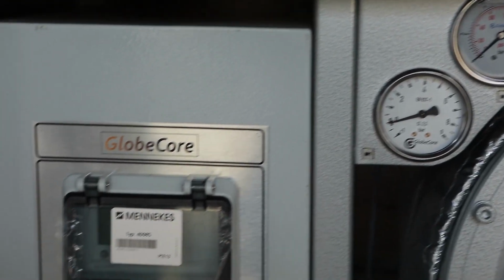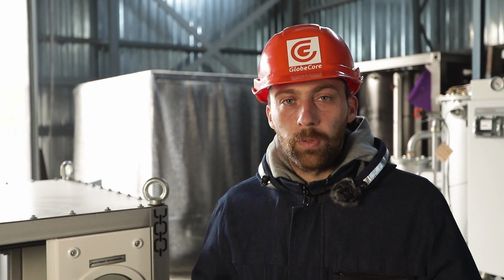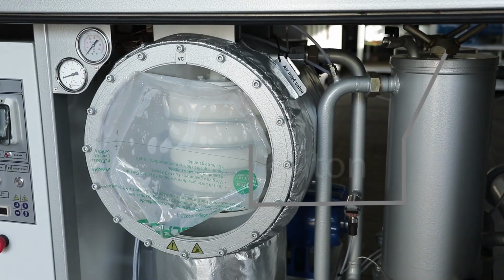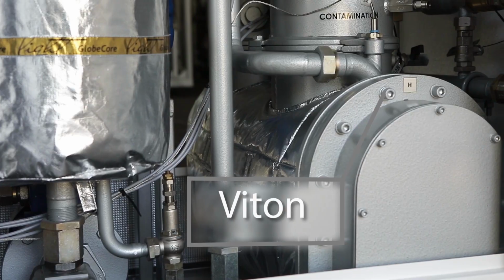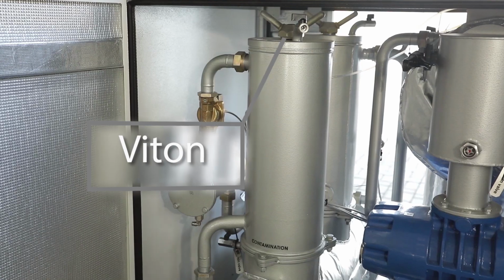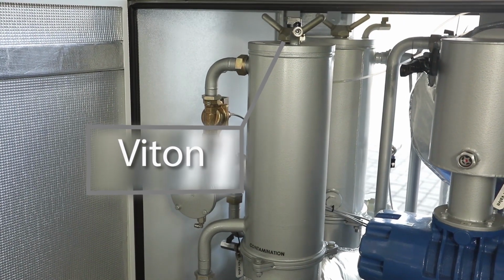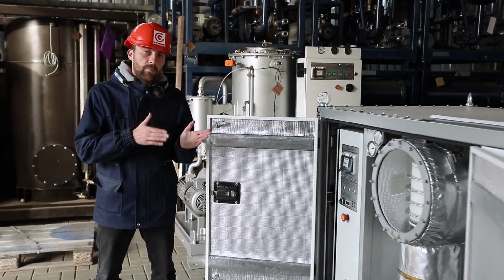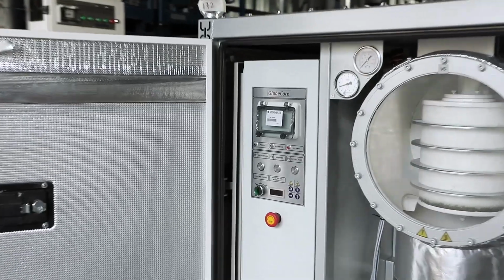Certain design solutions were required to enable the unit to operate in dusty underground environments. These include placing all the components in an assembled container, laying the power cables aside the pipes, an IP66 rating for the control cabinet. The unit also uses Viton-type seals resistant to various dielectric liquids. Controlling the UVM-1 unit is not difficult.